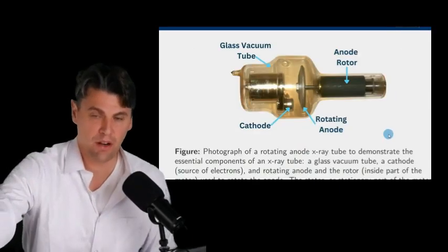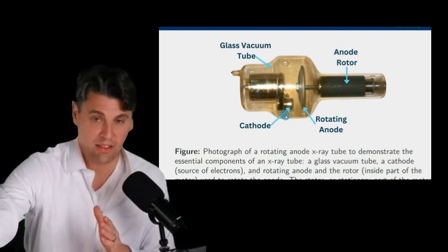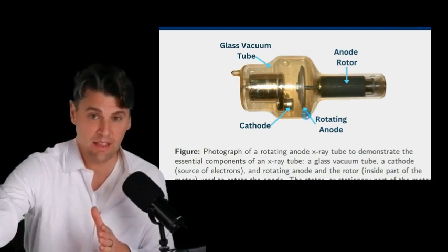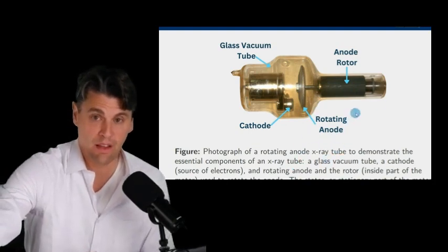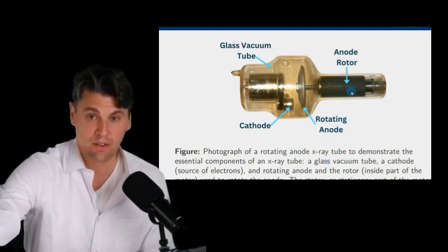Another view of a picture of what we call the insert. Right here is the cathode. Electrons come out, they will hit the anode while it's rotating, and then the x-rays will come down here. This is the insert. So this has the rotor, or the rotating part as well.